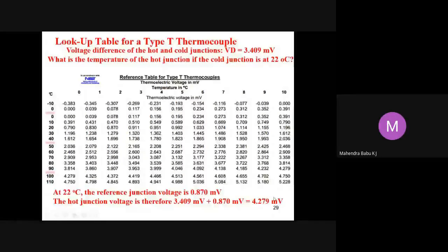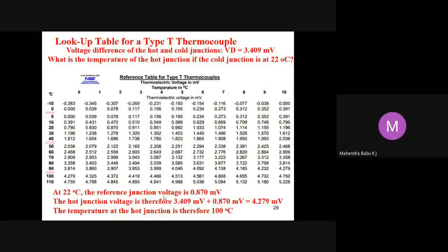Now corresponding to this millivolt value, you can find the temperature of the hot junction. Here we have 4.279, and the corresponding temperature is 100 degrees Celsius. Otherwise, it is 90 plus 10, which comes to 100 again. Therefore, the temperature at the hot junction is 100 degrees Celsius. Like this, knowing the voltage difference between the hot and cold junction, you can find the hot junction temperature if you know the cold junction temperature.